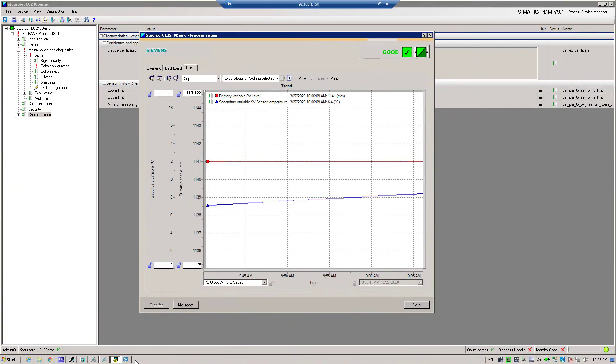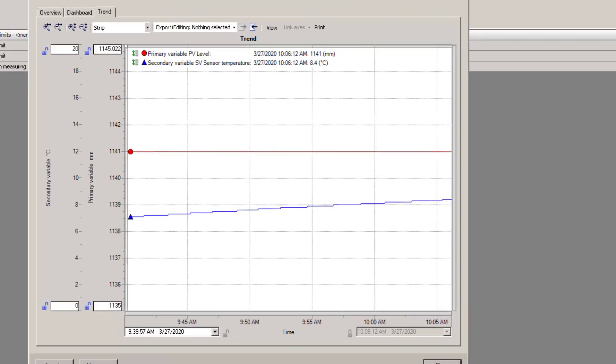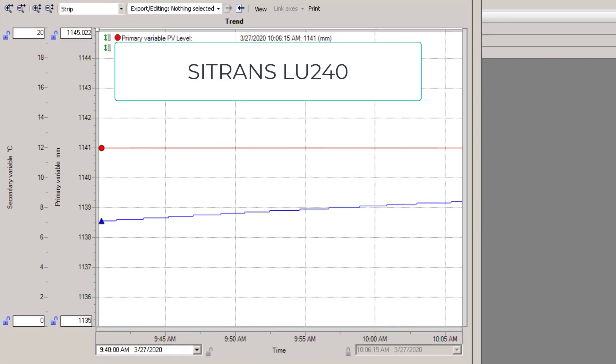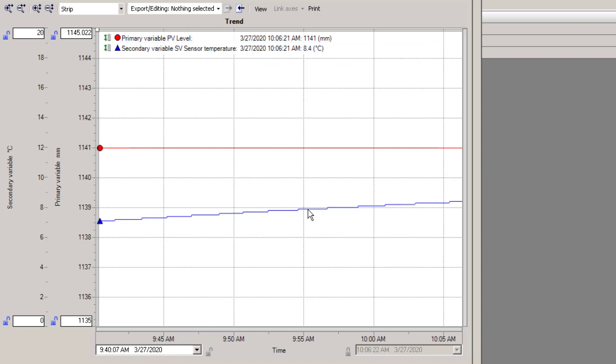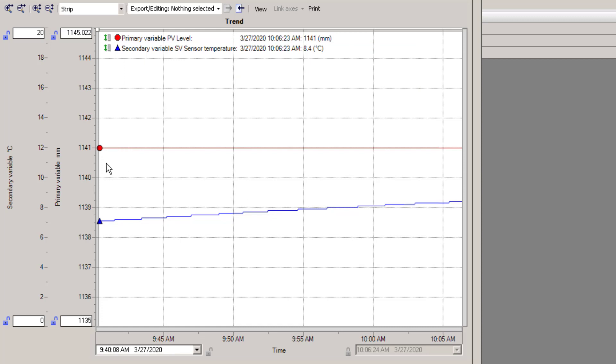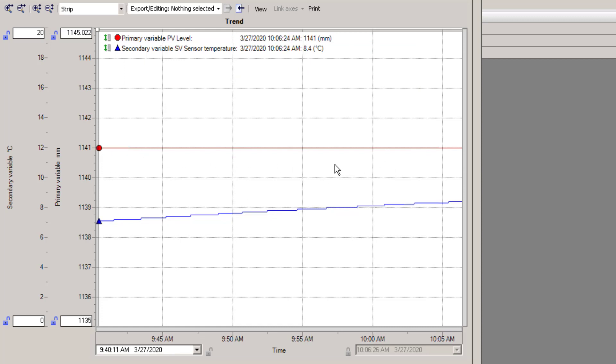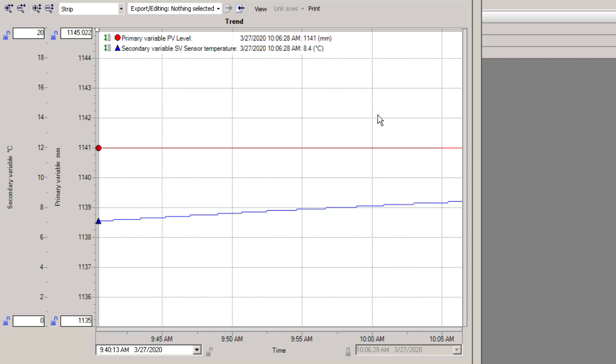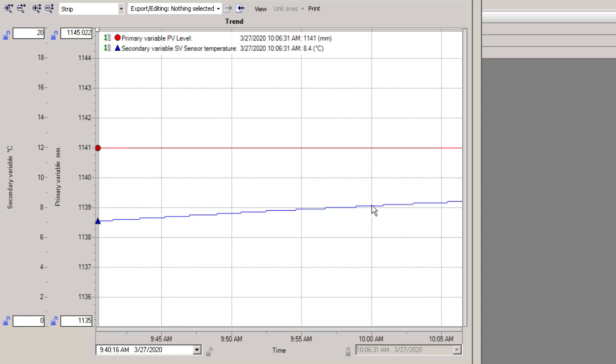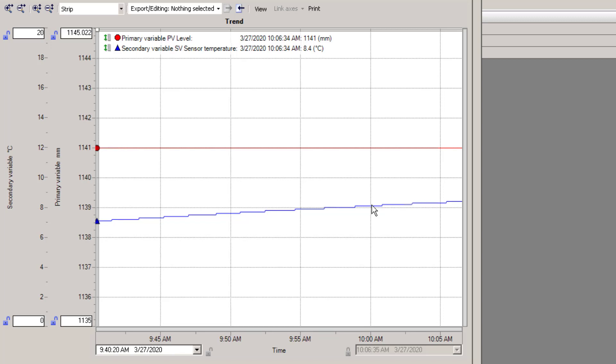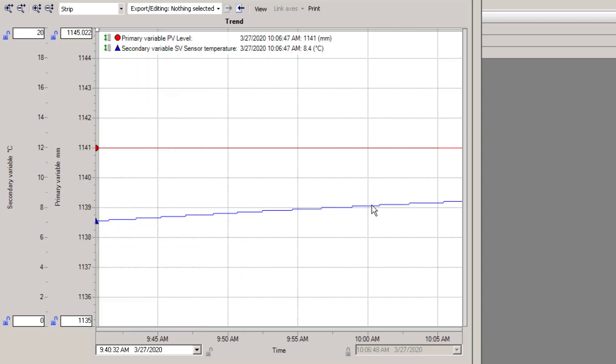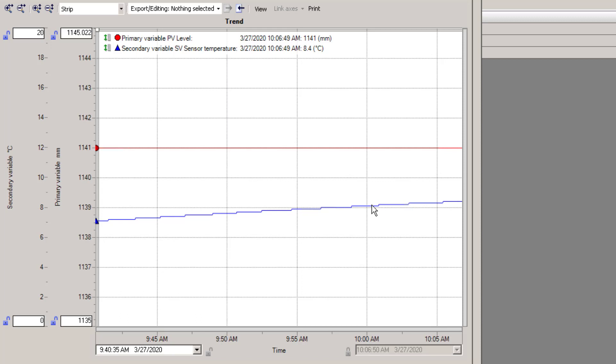Here we have a trend from the Sitrans LU240 probe. It's been going for over 20 minutes now with a fixed level reading and I put the units into millimeters so we can all understand what's happening. The transducer itself has a small amount of water on the front which we are going to dry off and see how it affects the reading.